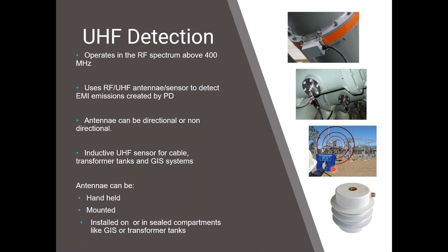This is a product that's a directional RF antenna designed for outdoor switchgear, where you can point it around, and since it's a directional antenna, it can very clearly identify the exact location where you're pointing it. So you're not just getting an emission from an antenna that says, yeah, I've got a problem here, and then walking around. With this one, by passing it around and scanning every insulator, every fitting, listening to and looking at the signal, you can identify exactly where that PD is happening.